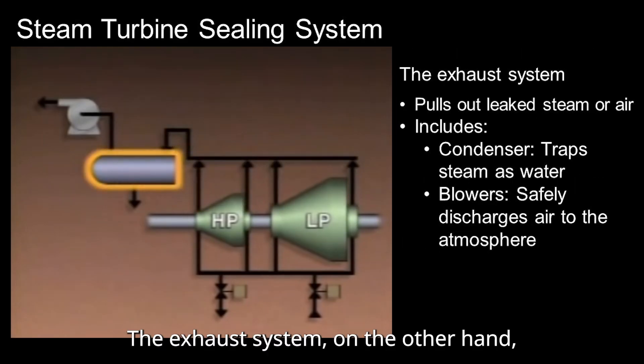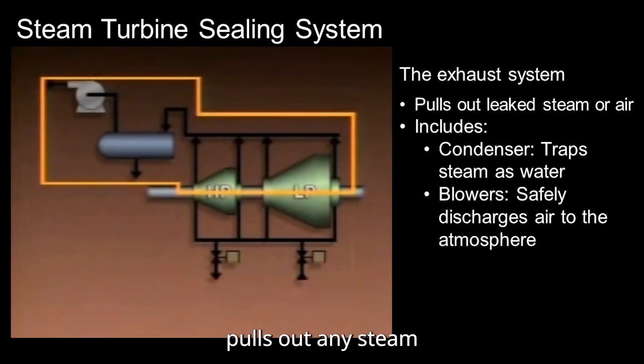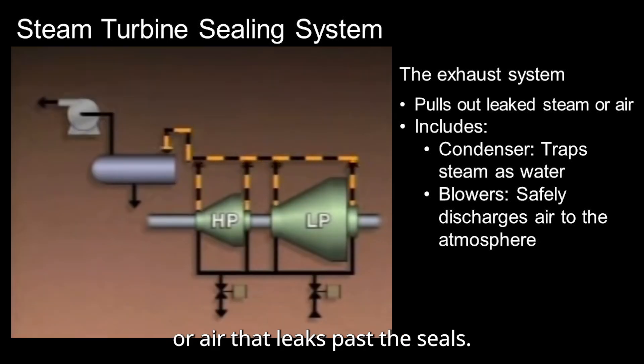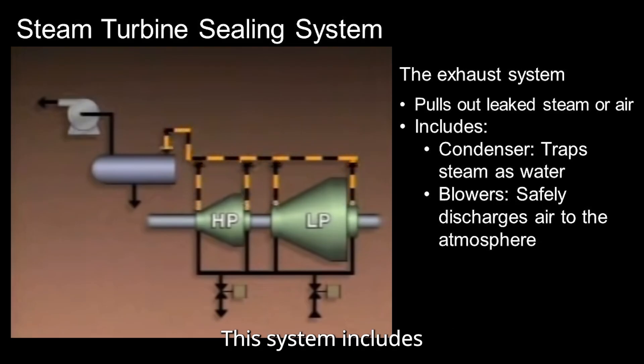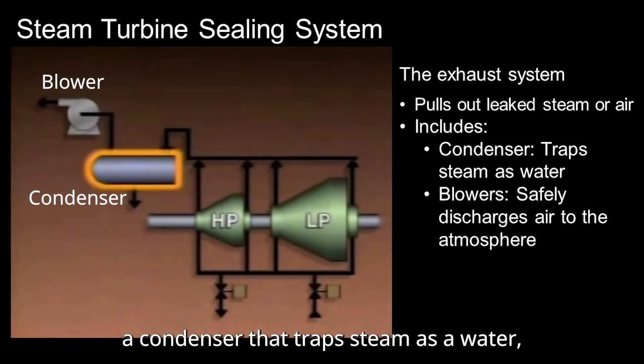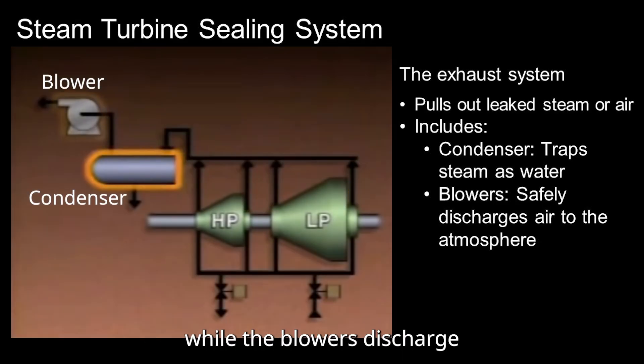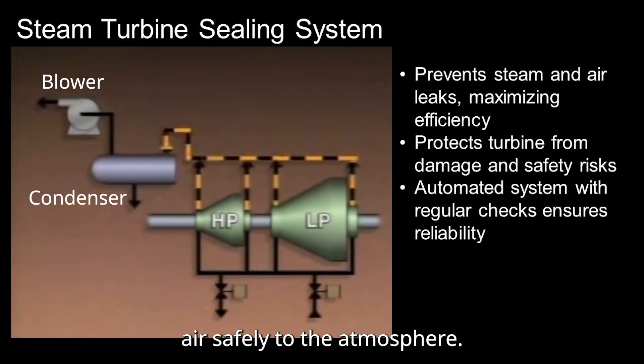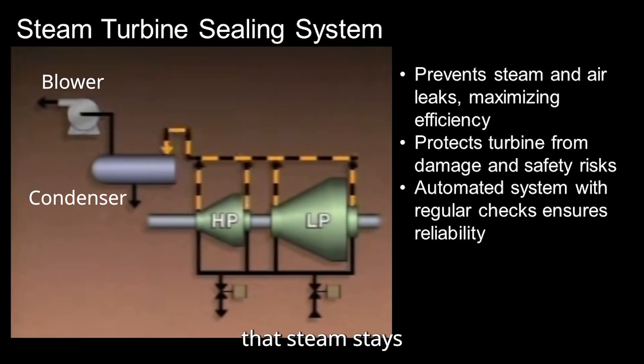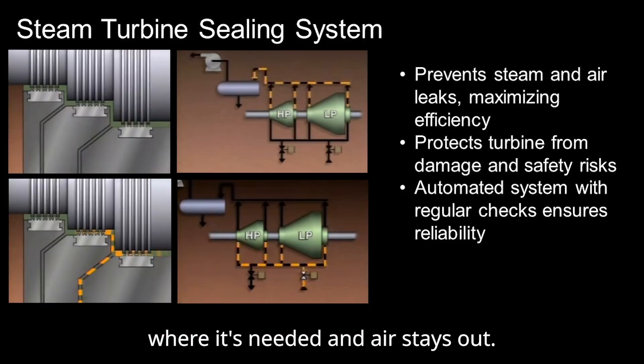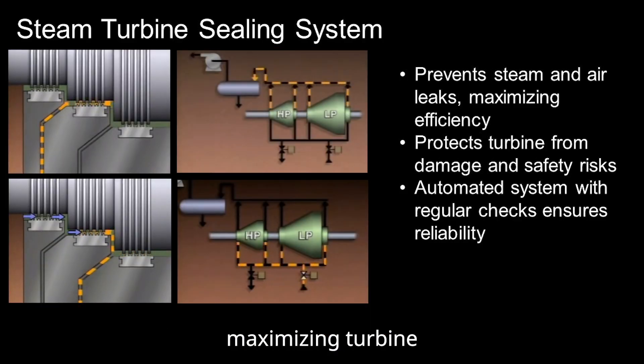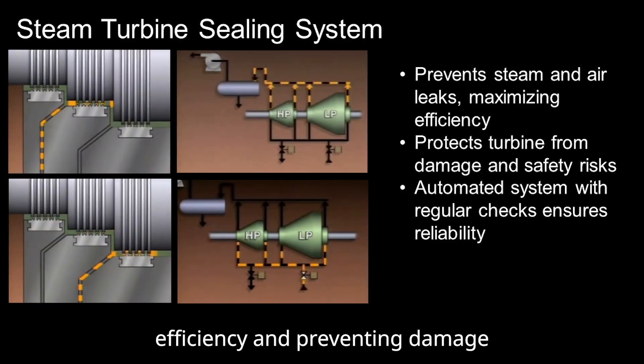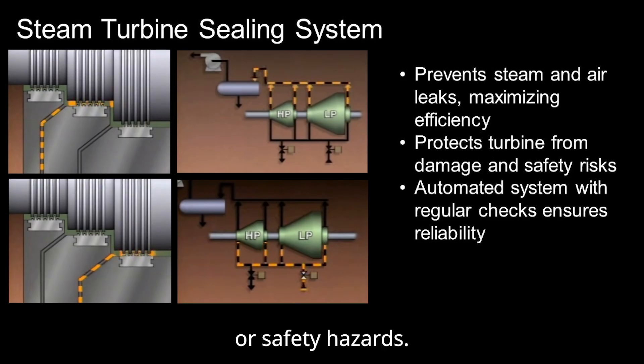The exhaust system, on the other hand, pulls out any steam or air that leaks past the seals. This system includes a condenser that traps steam as water, while the blowers discharge air safely to the atmosphere. Together, these systems ensure that steam stays where it's needed and air stays out, maximizing turbine efficiency and preventing damage or safety hazards.